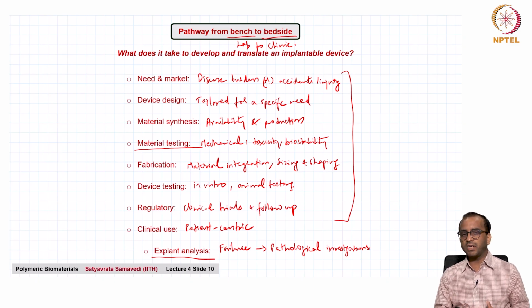They are specifically contextualized to a specific application, which is why the same material has to go through, again, very rigorous testing. Although it may have been approved many years ago for a specific application, for a new application as part of a different device, as part of being implanted in a different location of the body, where the conditions would be different, it still has to go through a series of rigorous testing.